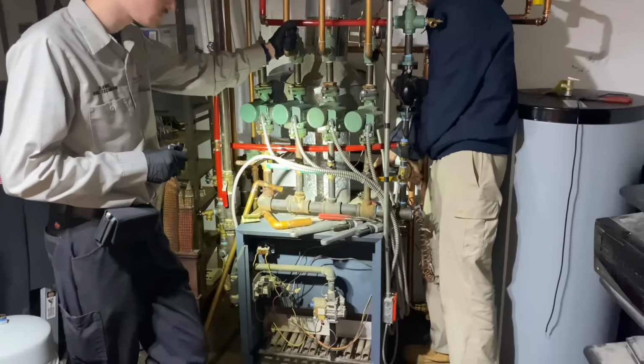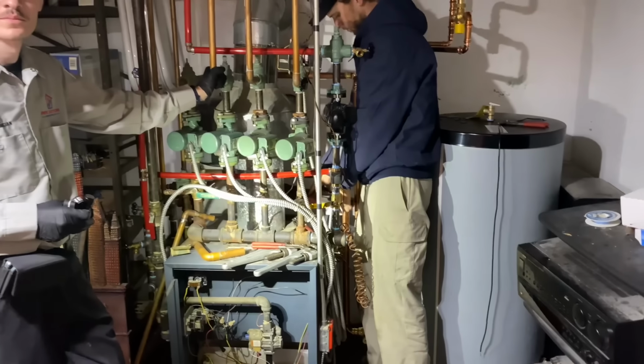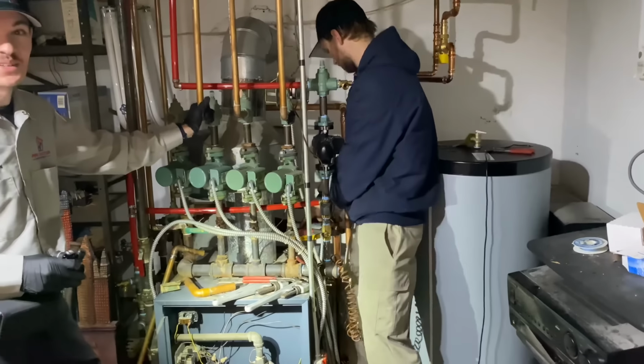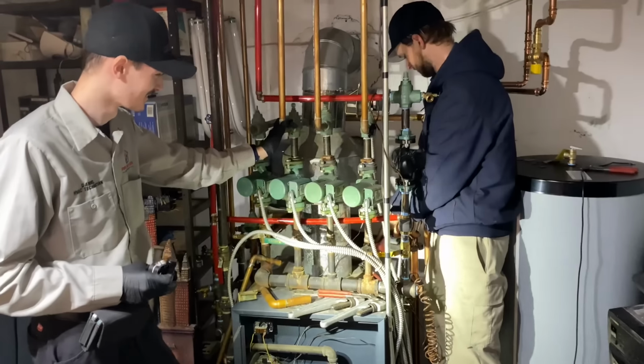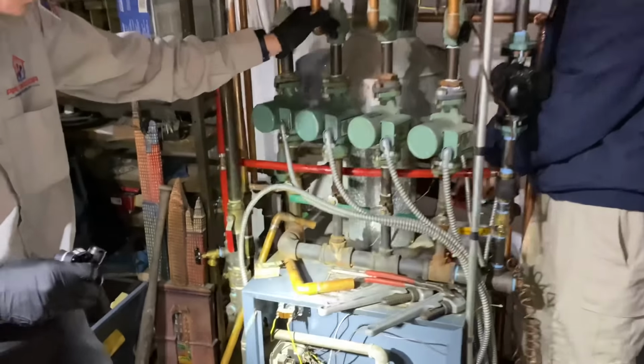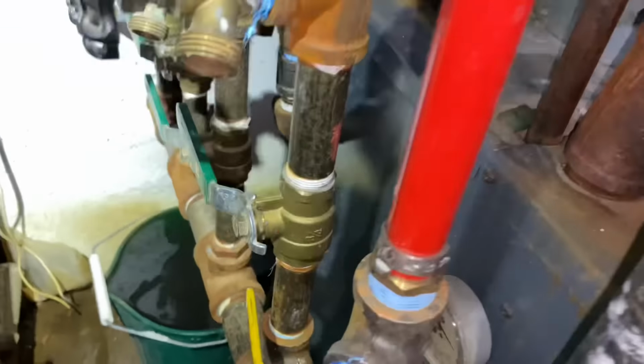So Daniel, while you're here, you had asked this morning while we were in the shop, is it a hard job? Is it a hard indirect? Looks real hard. Well, what we're going to change, though, is we have discharge, if you notice, on that relief valve right there. So we're going to change the relief valve, expansion tank, and pressure-reducing valve.